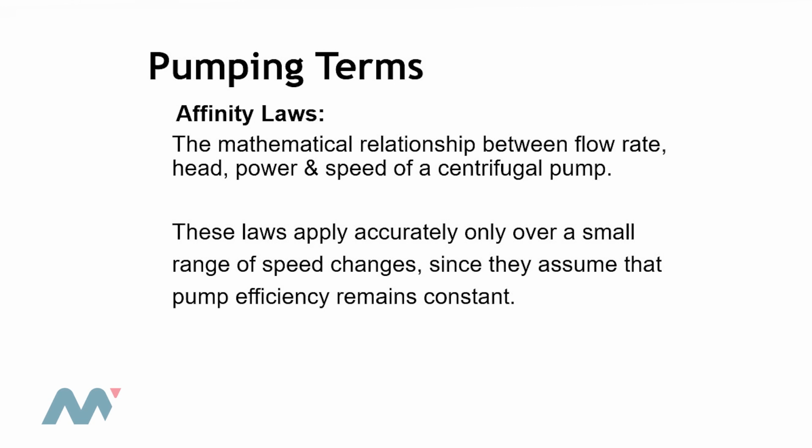These laws apply accurately only over a relatively small range of speed change, and they assume that the efficiency of the pump doesn't change, which is not 100% correct, but it's useful in terms of translation of performance.